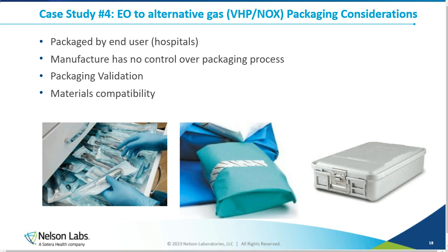If you're doing that, that doesn't necessarily absolve you of running a packaging validation. So I would suggest, if that was the way you were going, you'd think about the customer impact, because hospitals prefer to use sterile devices rather than sterilizing their own. They do have a lot of these units available to them in the hospital, and they can use them to package and sterilize items. Generally, though, these are not single-use items. They're usually reusables.